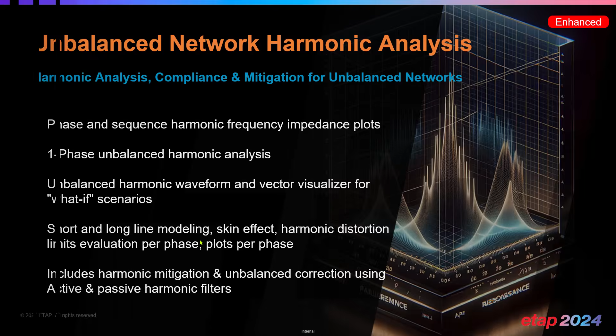These static filters have been enhanced so we can automatically size the high pass, damp filters, as well as the third order, including their subtypes, automatically within ETAP at a press of a button, making sure you can size the filter not only for power factor correction but also for harmonic mitigation, both at the same time, while considering the economic impact of sizing these filters.